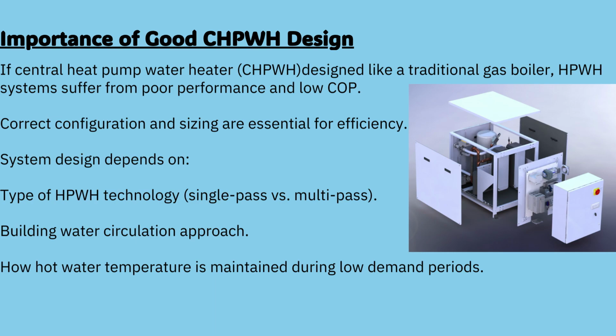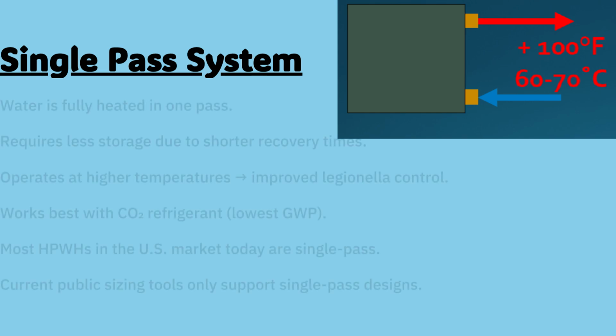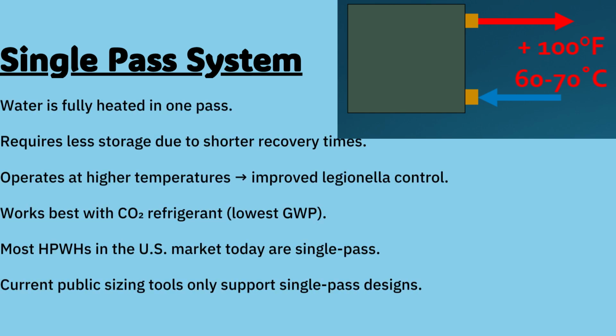That choice depends on several factors: the type of heat pump technology used, how water is circulated through the building, and how water temperature is maintained when hot water demand is low. In the US, two main categories of heat pump water heaters are sold today: single-pass and multi-pass systems. In a single-pass system, incoming cold water is fully heated in just one pass through the heat pump. These systems recover faster, which means they require less storage capacity.